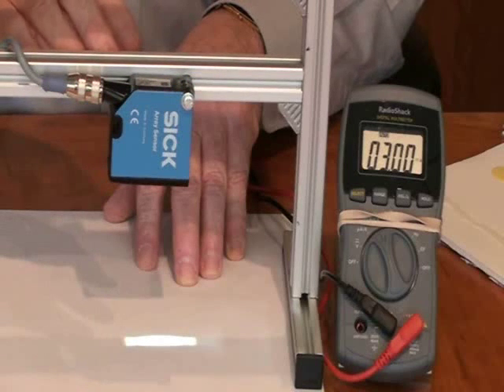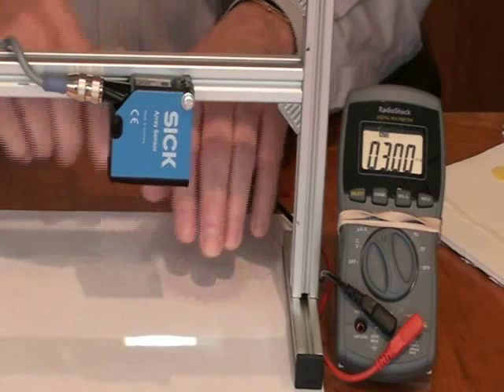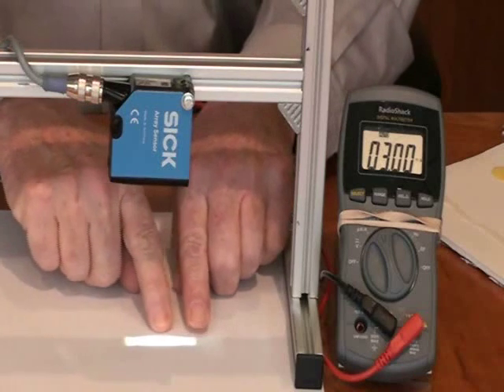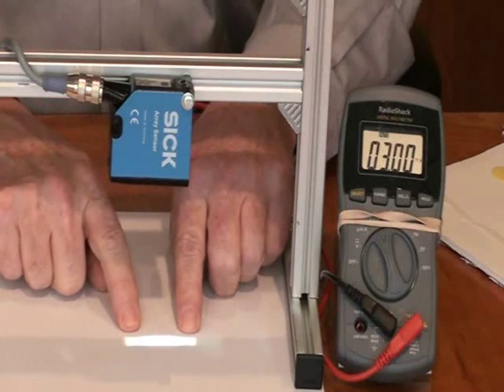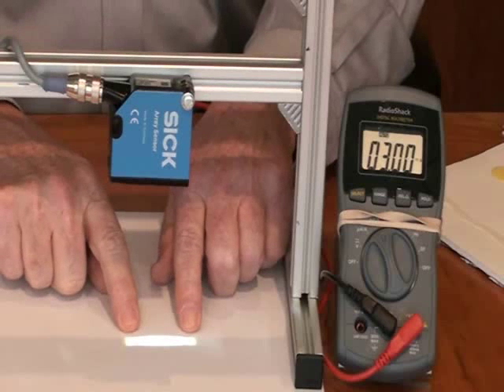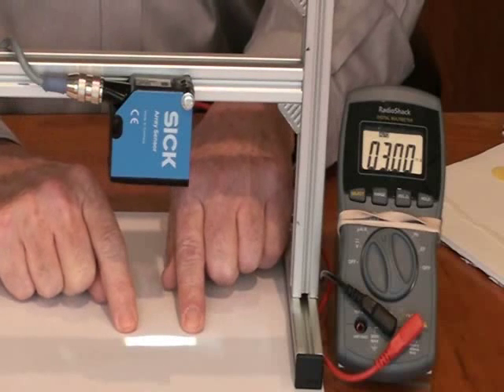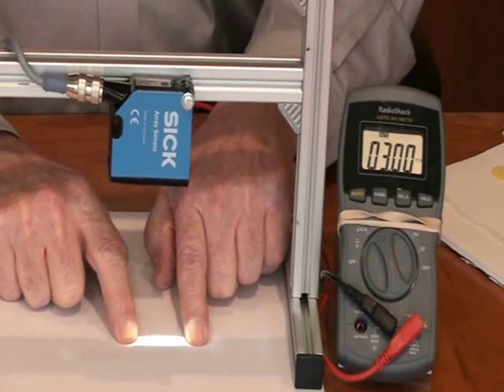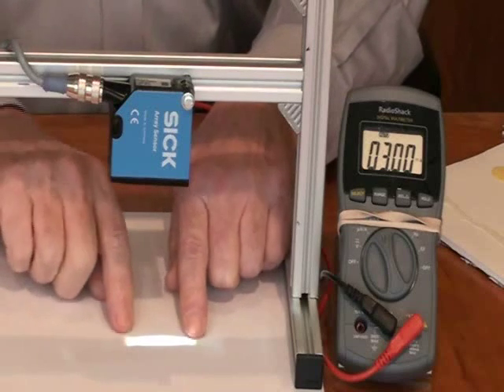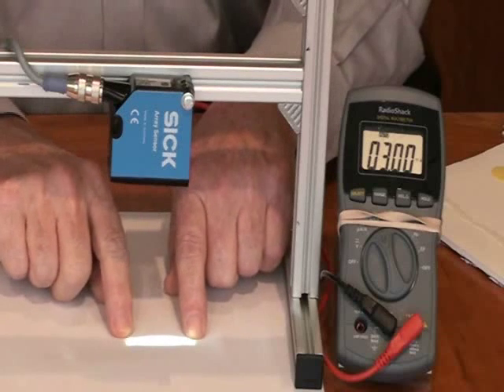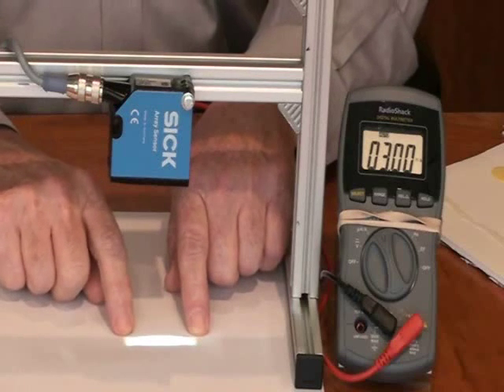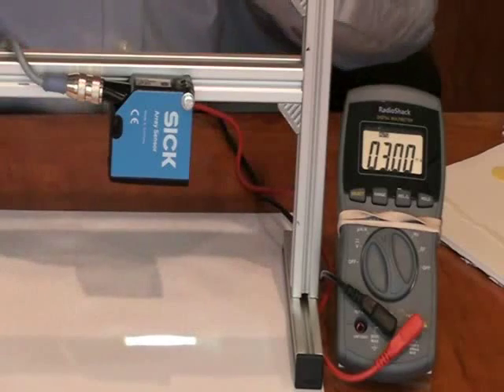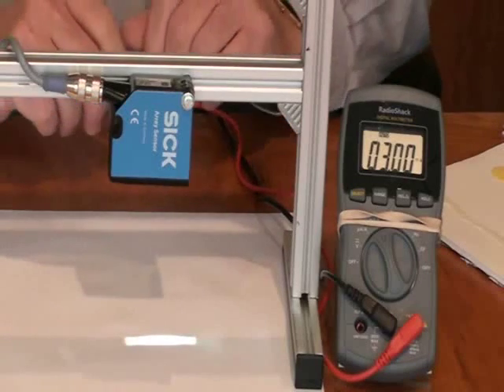It's in a diffuse mode or a prox mode right now, and what that's doing is shining this white LED light down onto the surface, white piece of paper here, and the actual size of the spot itself is 30 millimeters long by 10 millimeters wide. You're seeing a little bit of residual light along the sides here, just like you would with a flashlight, where you have a more intense beam and then residual light to the side.